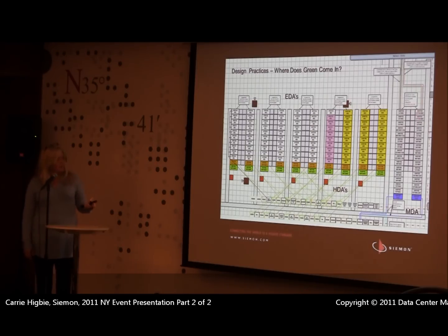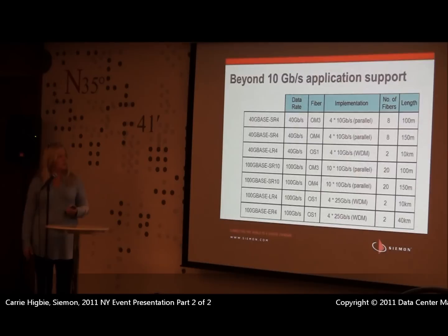This is kind of how it looks. So we've got server cabinets, we've got primary network, secondary network. In this particular data center, they're at the end of the row just because they're on different fire suppression zones, but you can have one whole row of primary, one whole row of secondary, and then it comes down into this distribution zone. So I can connect any of these server cabinets to primary or secondary. If I add a few more servers and I don't have the capacity or networking doesn't have a budget to buy another switch, I can borrow switch ports off the adjacent zone until I build up enough need to buy another switch.